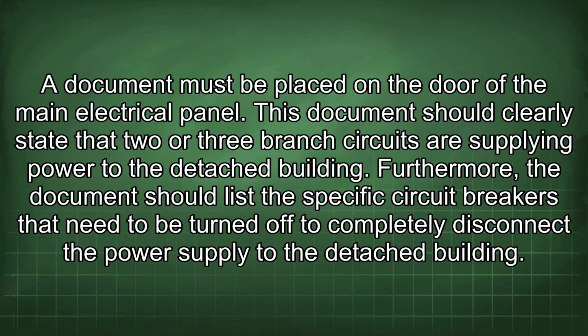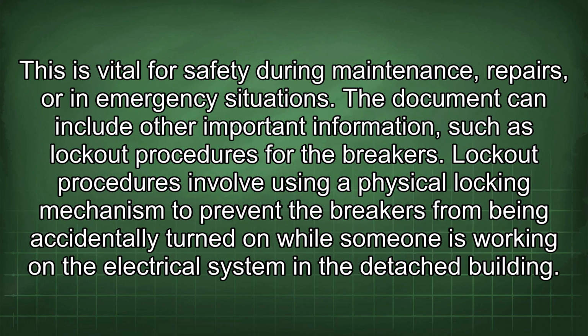A document must be placed on the door of the main electrical panel. This document should clearly state that 2 or 3 branch circuits are supplying power to the detached building. Furthermore, the document should list the specific circuit breakers that need to be turned off to completely disconnect the power supply to the detached building. This is vital for safety during maintenance, repairs, or in emergency situations.